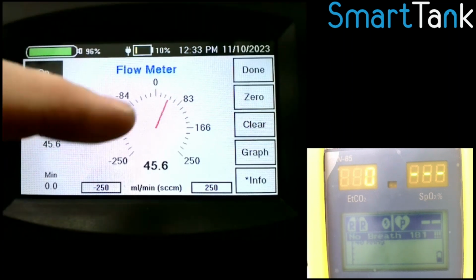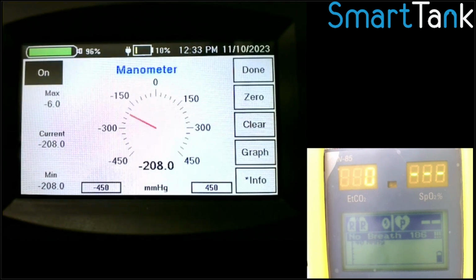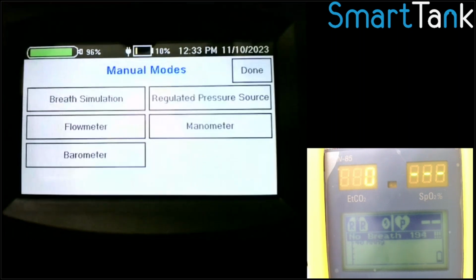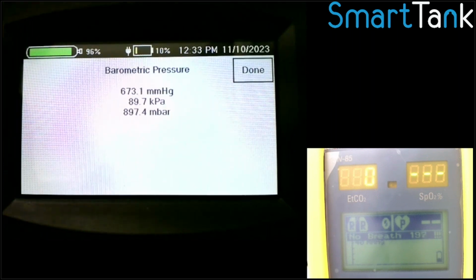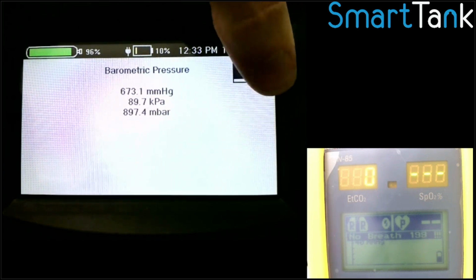So in this case, we're still getting a good positive flow because it's still running. Or I can switch it over to show a manometer. In this case, it's a vacuum that's being drawn because it's drawing that sample out of the SmartTank. And so in this case, it's a good vacuum gauge. You can even get to the barometer readings if you just need to see what those are for something else.